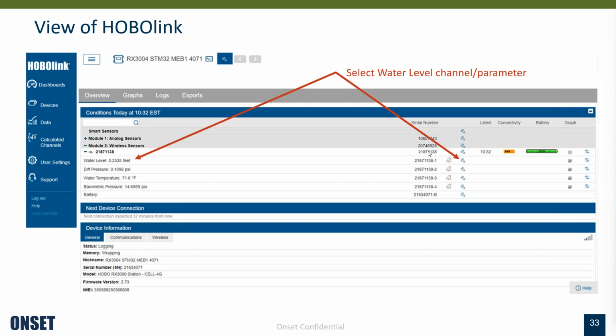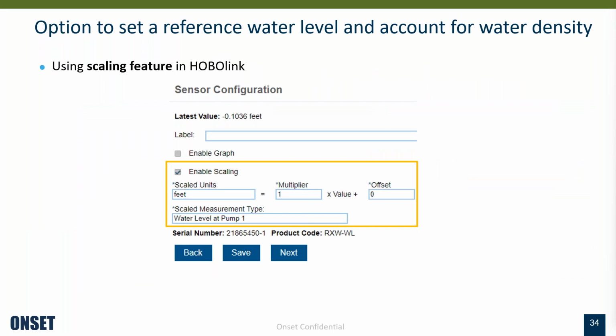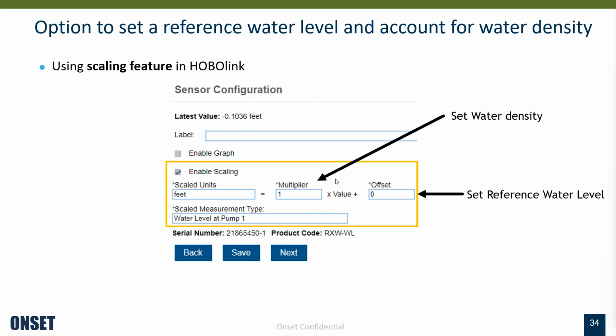Regarding water level or water depth, as I mentioned earlier, you can use it to set a reference water level or account for water density. We have a scaling feature in HOBOlink that lets you add a multiplier and an offset. We leverage that multiplier to set your water density. Fresh water would be one, so it doesn't impact the reading, but for brackish or salt water you may want to use a different value. Accounting for water density is optional, but it gives higher accuracy. The offset then lets you set the reference water level.